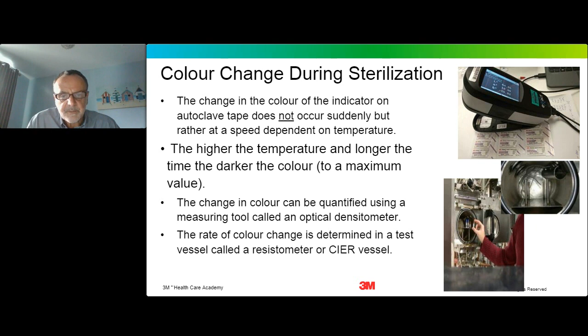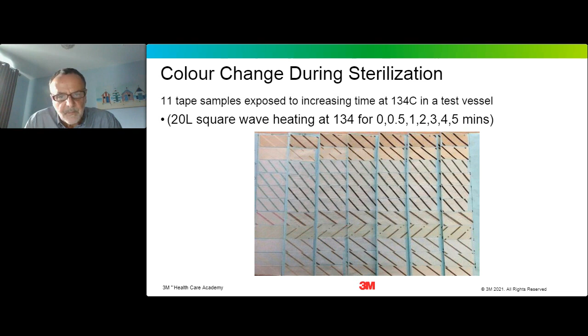So if you look at this slide, you can see a number of samples of autoclave tape from different manufacturers that have been exposed anywhere from 0 up to 5 minutes, at 134 degrees, in a steam test vessel. And you can see from this picture how the autoclave tapes will change colour as they are exposed to different lengths of time of exposure. And we can also quantify those colour changes using this densitometer. And if we plot the optical density of the measured colour against time of exposure, you will get a typical set of curves like this, which are shown on this chart.